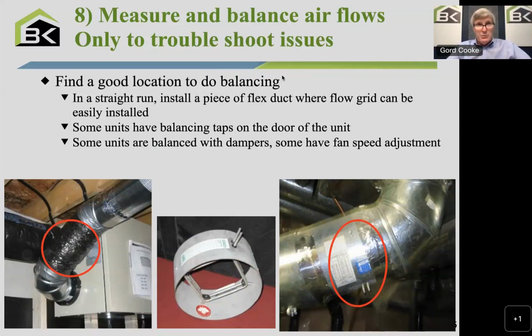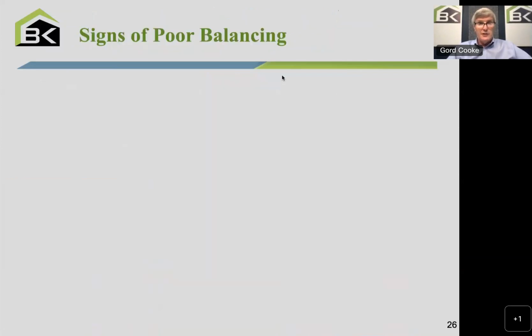And I would say if a community is looking after the maintenance of units, then you'd probably want a balancing kit on hand for the community. Not everybody needs this. Not every unit needs it. It's for new construction, new projects, and to troubleshoot problems with units out in the field. You've checked the fans, they're operating, but there's no airflow. It may be a balancing issue. Seldom does this have to be done on a regular basis, only if you're looking for problems inside that unit. And of course, you always follow the manufacturer's procedures. Different manufacturers have different devices. This balancing kit that you see here, this grid, could be used on anybody's unit, but sometimes manufacturers have other elements that you can use.